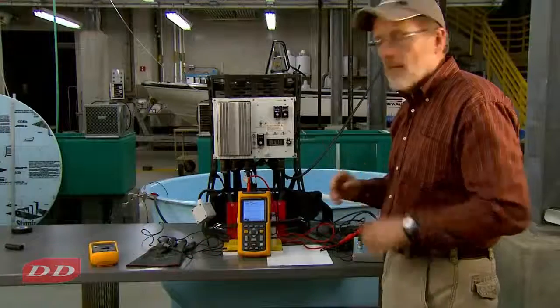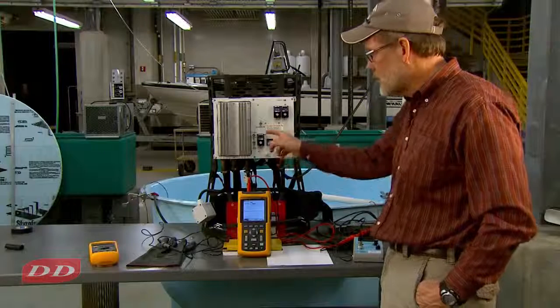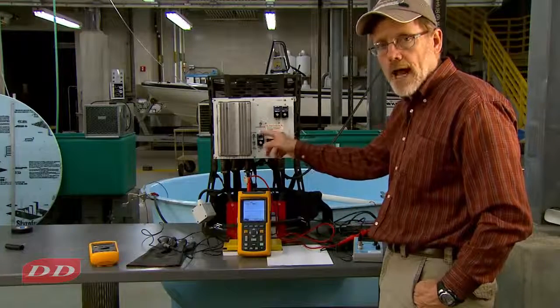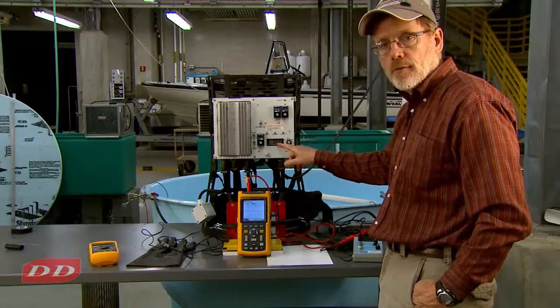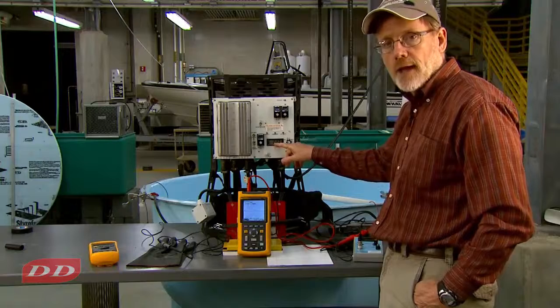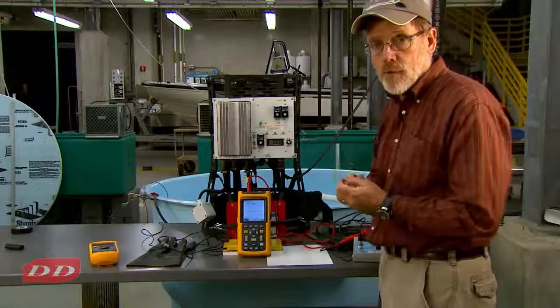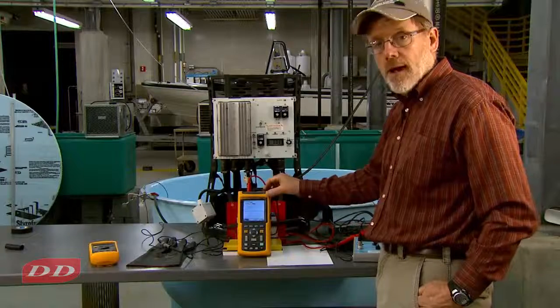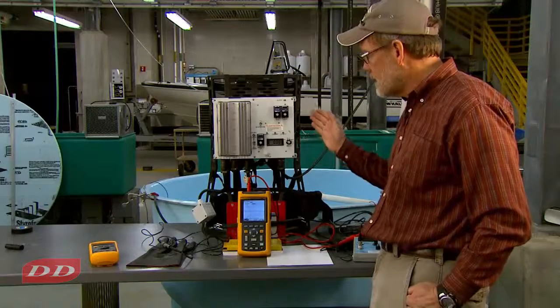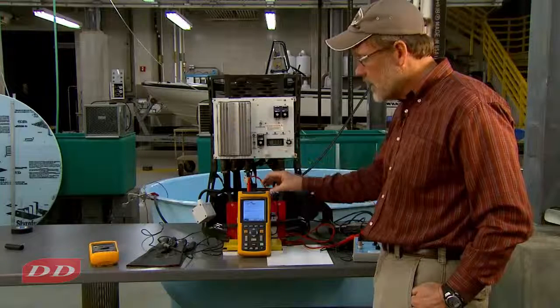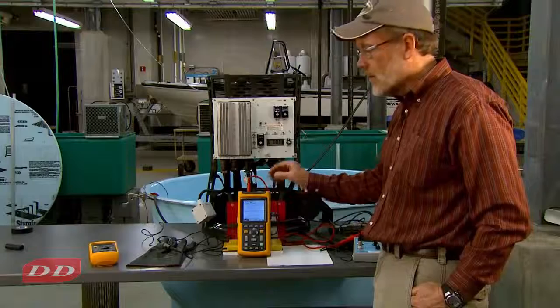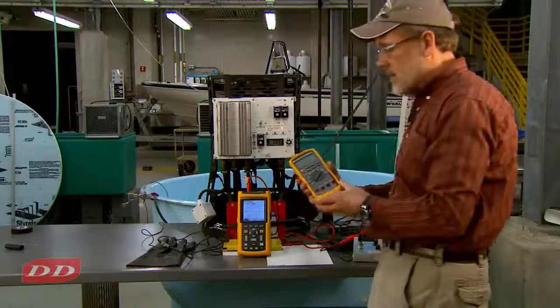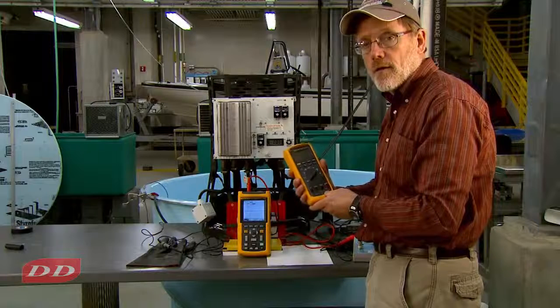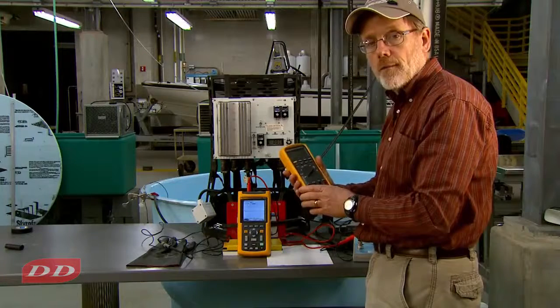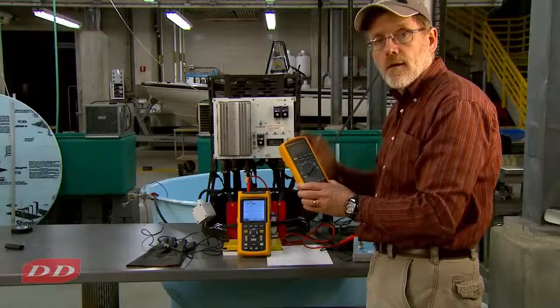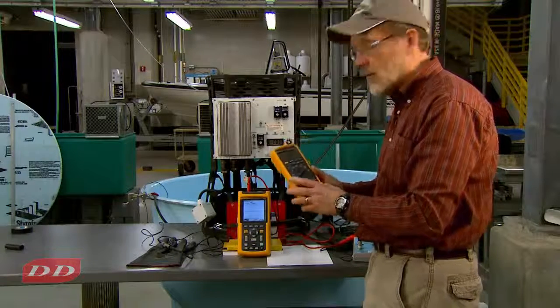The next calibration check we'll make is on the voltage setting. So we'll look at the voltage setting, which is what we dial in, what we get out, and the voltmeter here is what is displayed, actually what we're getting out. Now you'll use two different pieces of equipment for that, a scope meter and a multimeter. Now we're using pulse direct current, so a scope meter is very good for measuring pulse direct current. Multimeters are oftentimes not suited for pulse direct current measurements, but there are a few on the market that do measure peak voltage on pulse direct current. So we have one of those meters here.